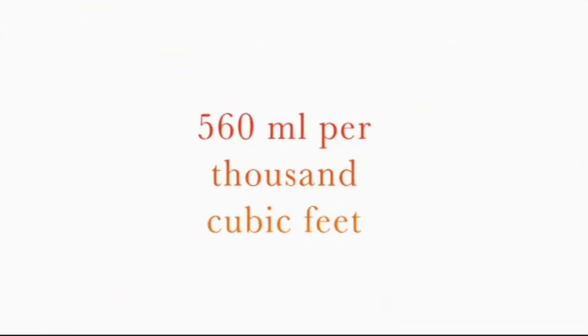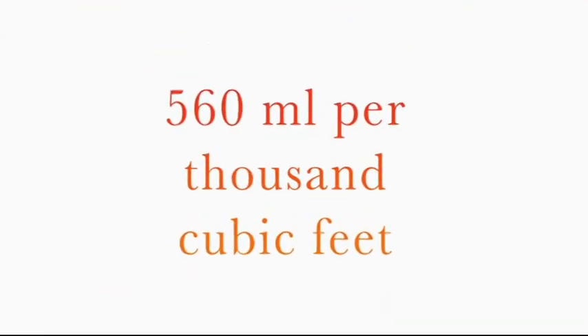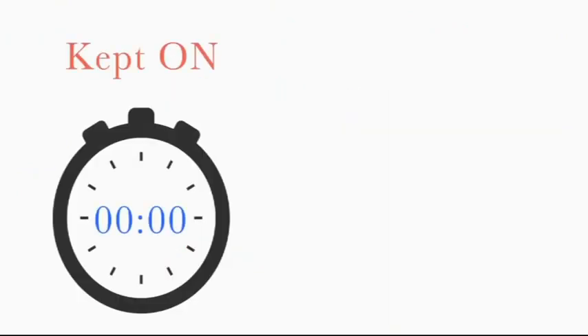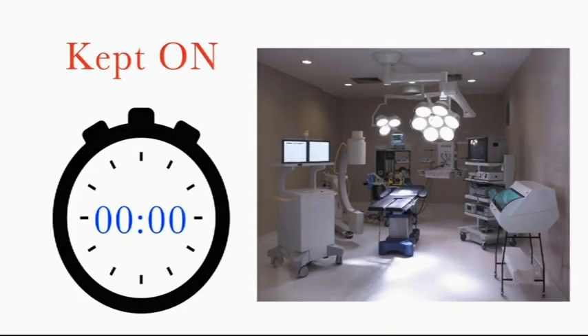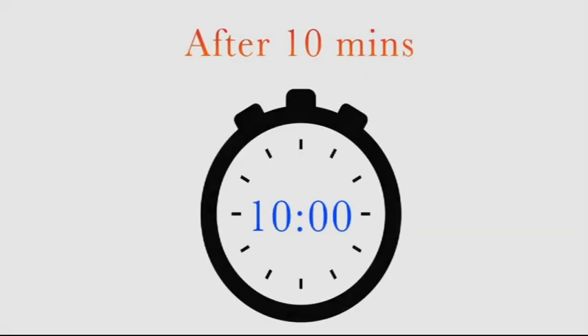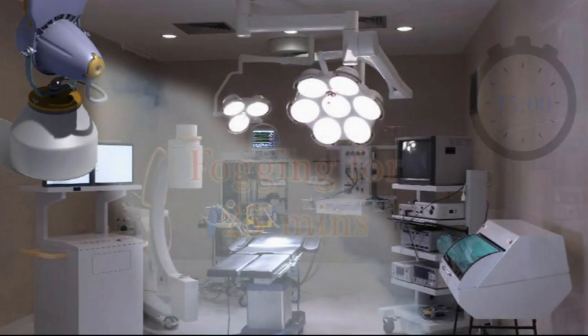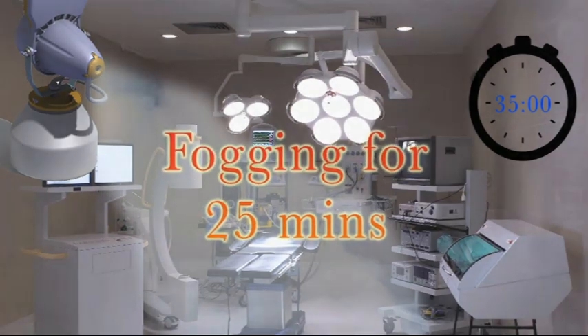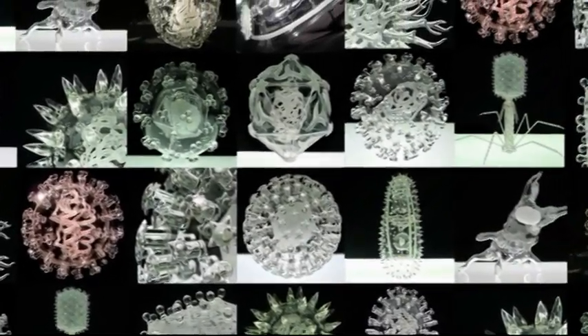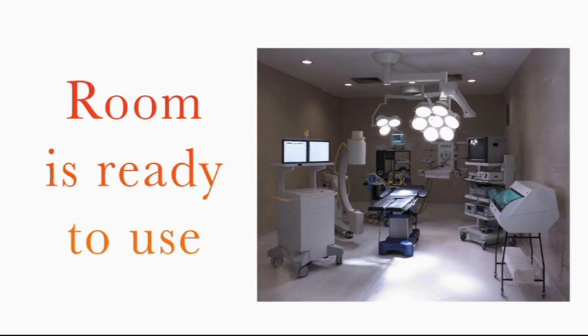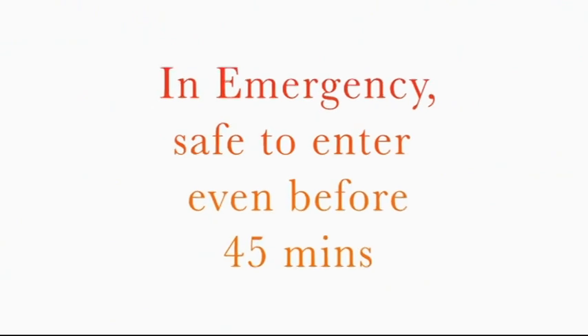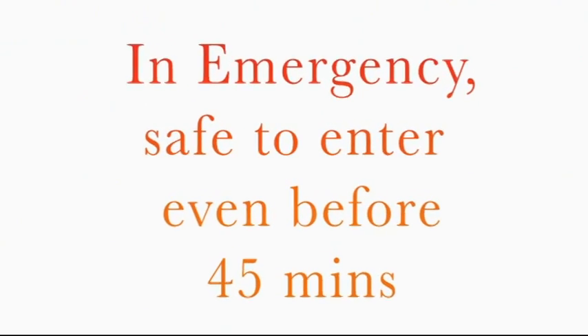Please use a fogger that generates a mist of particle size less than 10 microns. The solution requirement is 560 ml per 1000 cubic feet. AHU should be kept on for the first 10 minutes of fumigation. Switch off the AHU after 10 minutes. Fumigation should be done for 25 minutes after switching off the AHU. After fumigation, the room is to be closed for 45 minutes to provide sufficient contact time with the microorganisms as well as drying. The AHU can now be switched on and the room is ready for use. In case of an emergency, the room is safe to enter even before the 45-minute waiting period is over.